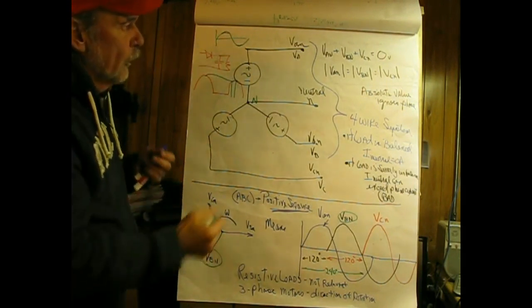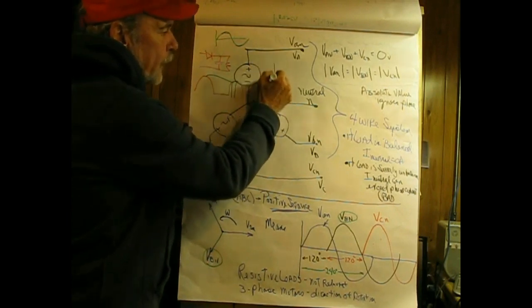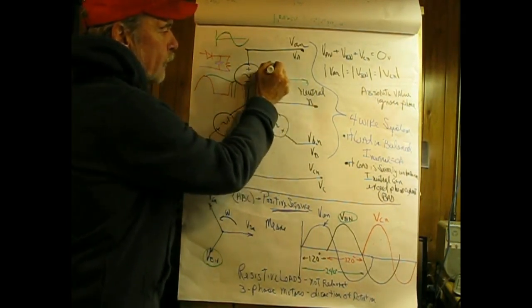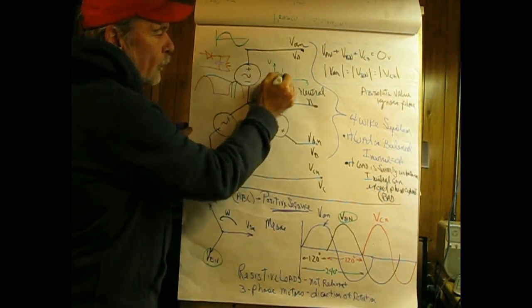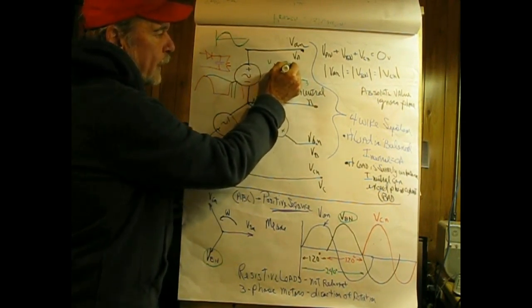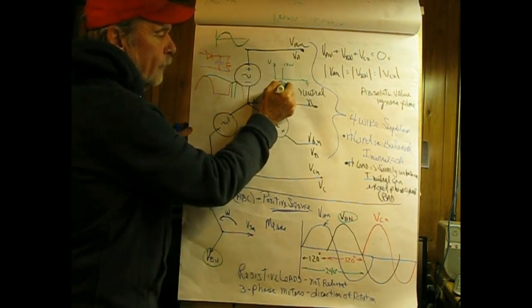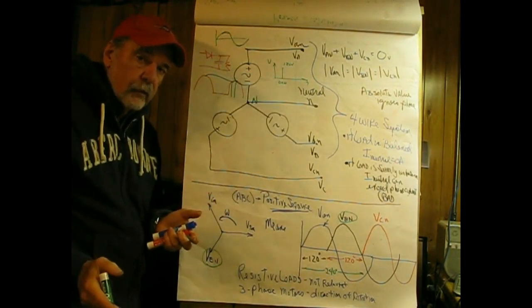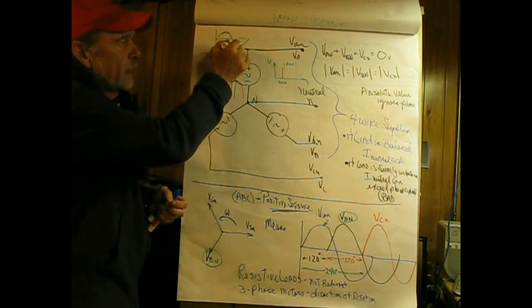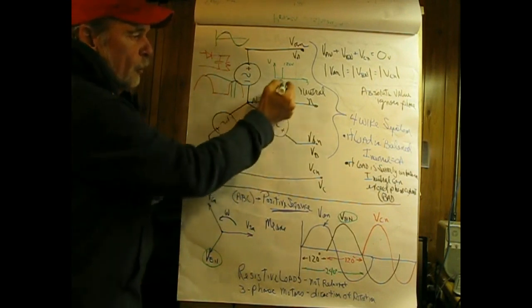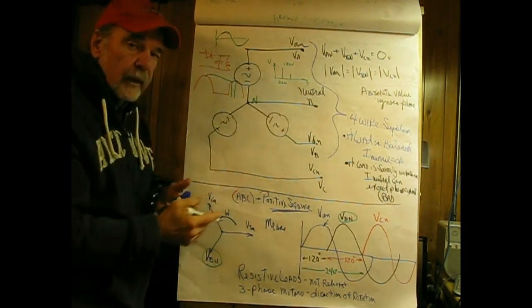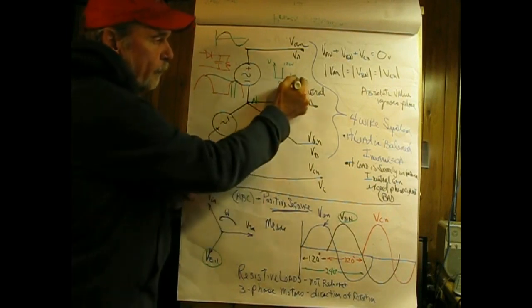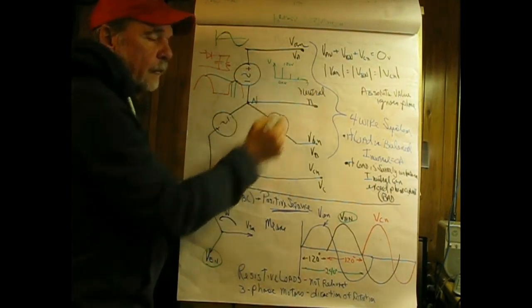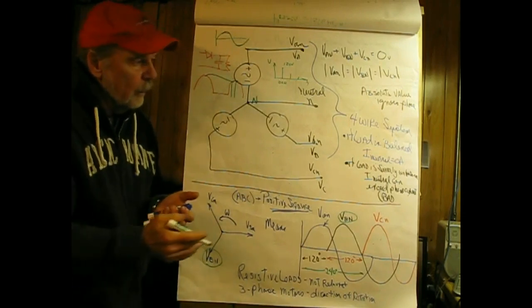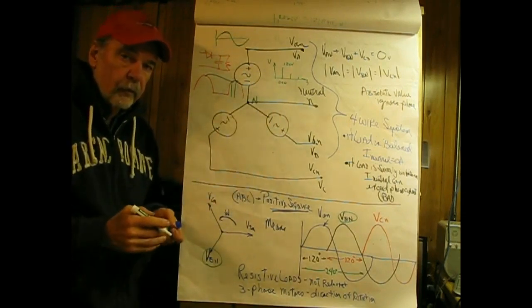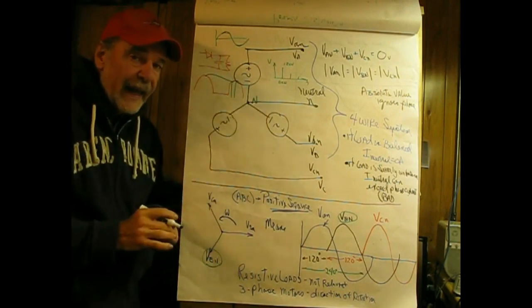So, if we were to look at this, say in the frequency domain, where this would be F, and this would be the voltage V, what we would see would be one spectral spike at 60 hertz equaling 120 volts RMS. Now, if we start to round the top a bit, we generate a third harmonic, which is a sine wave 3 times the frequency, and a fifth harmonic, and a seventh, and a ninth, and so forth. Now, what a triplen is about is the third harmonic in multiples of 3 in these loops add together.